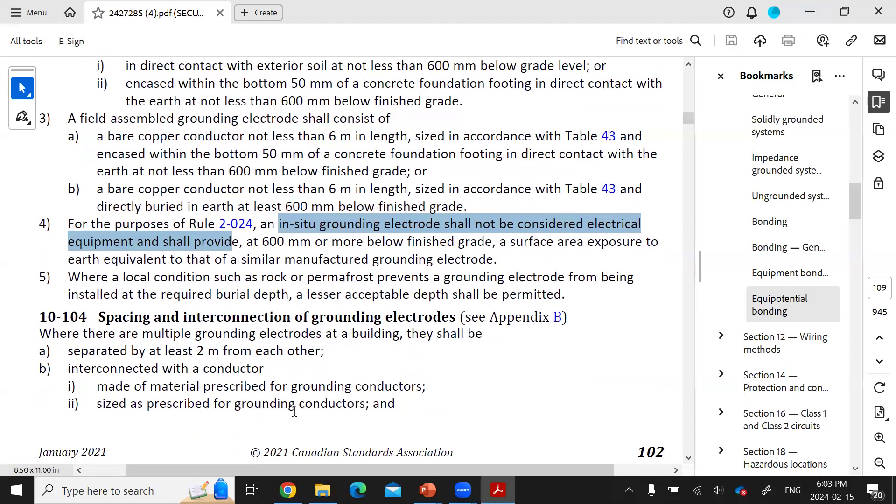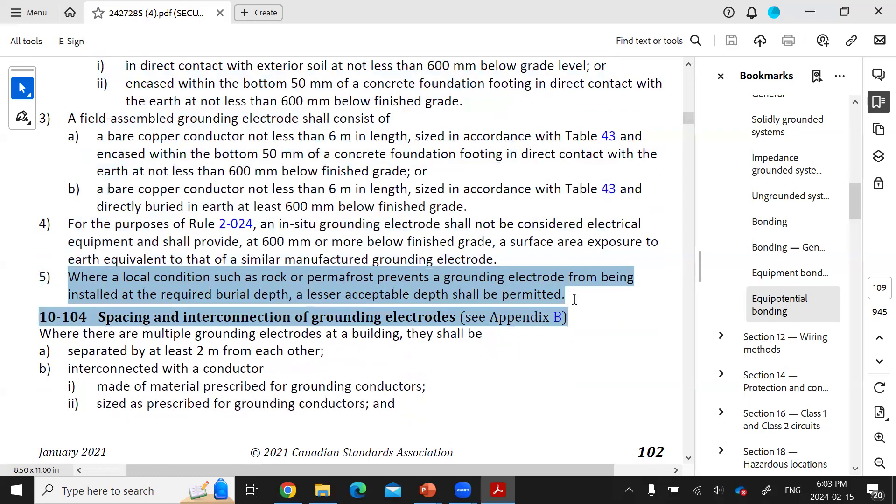Sub-rule 5 says where the local conditions such as rock or permafrost prevent the grounding electrode from being installed at that burial depth, a lesser acceptable depth might be acceptable. But in this case, you have to make sure that your local inspection authority is going to make the final determination about what the most appropriate depth would be.